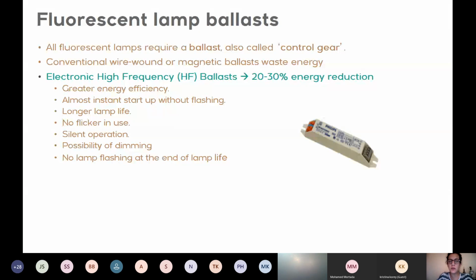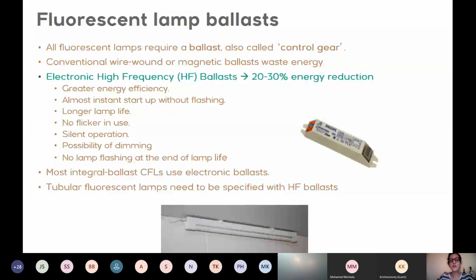So what can you do to improve that? You can use electronic high-frequency ballasts. These can save 20 to 30% in energy for the lamp, start up the lamp without any flashing, increase its lifetime, and they don't flicker and have a silent operation. Most integral CFLs or compact fluorescent lamps already have electronic ballasts, but if you're using tubular fluorescent lamps, you have to specify that you want a high-frequency ballast with them.